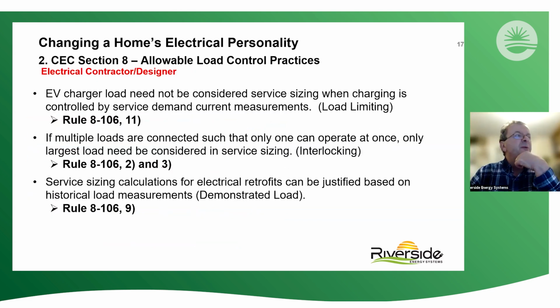And then in Section 8, as I mentioned, there are some other rules which are not paid as close attention to all the time, although they're gaining more traction lately. For instance, if we're using an EV charger in the building, if we use a service demand controlled switching device that does not allow the charger to work unless there's sufficient margin left in the service, we don't even have to include it in our service calculation. So that's a really great feature to harness.